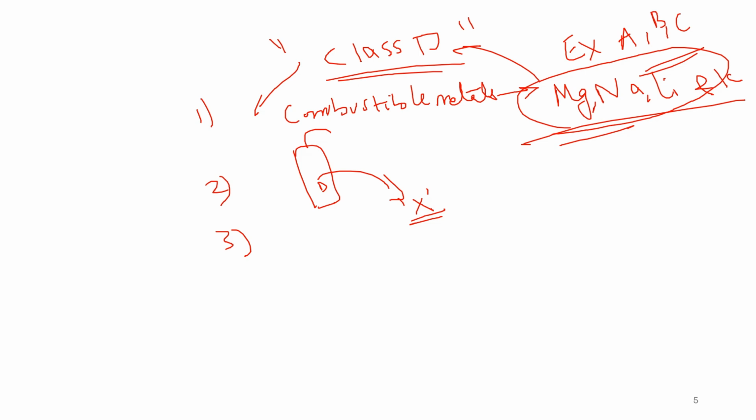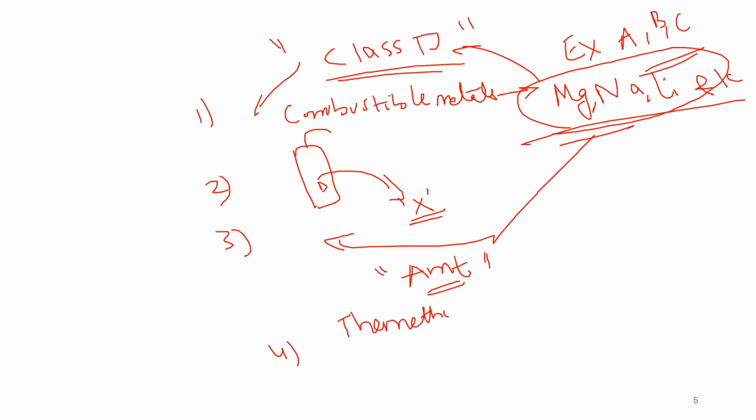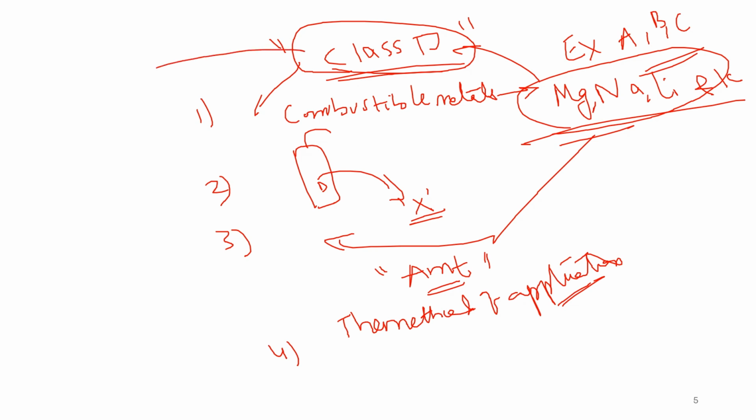And third point, extinguishers and agents for use on combustible metal fires are rated for the amount of agent. That's the reason the manufacturer has to recommend the quantity of Class D extinguisher based on the amount of agent. And the final point is the method of application needed to control the fire. The most important point to be noted is that Class D extinguishers will be selected based on the manufacturer recommendation only.